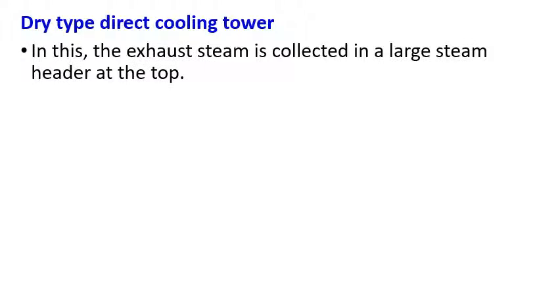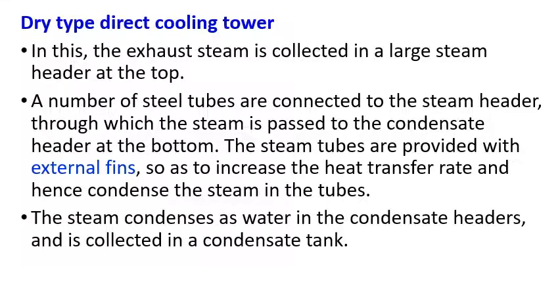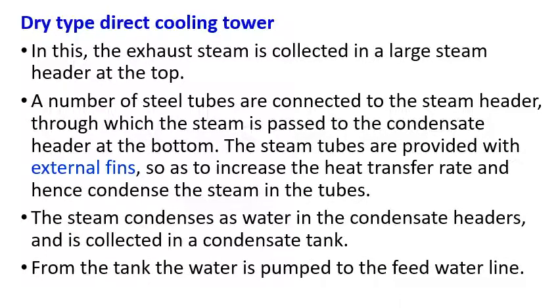In the direct type dry cooling tower, the steam is collected in a large steam header at the top. Steam tubes are provided with external fins to enhance heat transfer, and the steam condenses into water in a condensate header, which is collected in a condensate tank. The direct type requires less water compared to wet cooling towers. Water from the tank is then pumped to the feed water line.